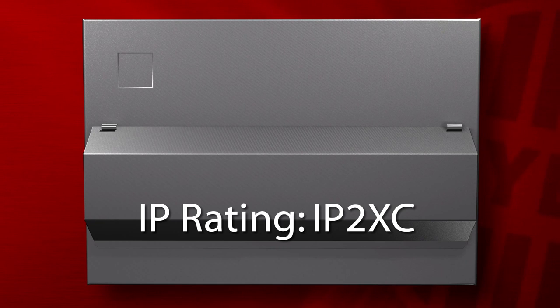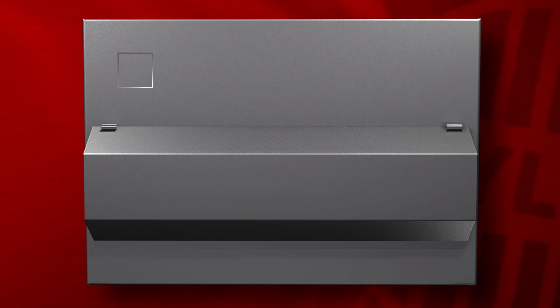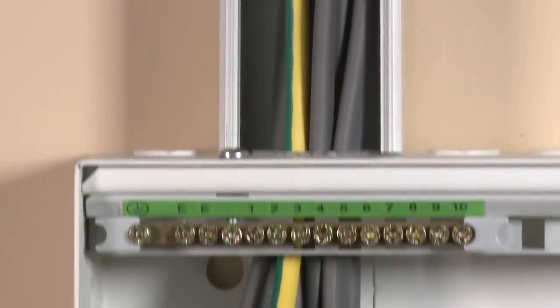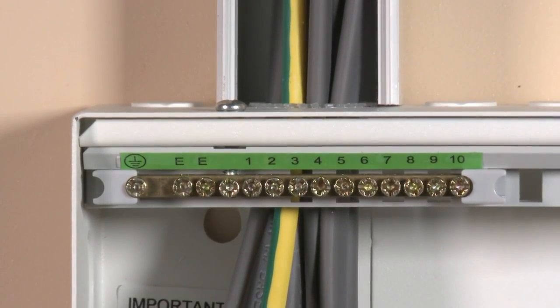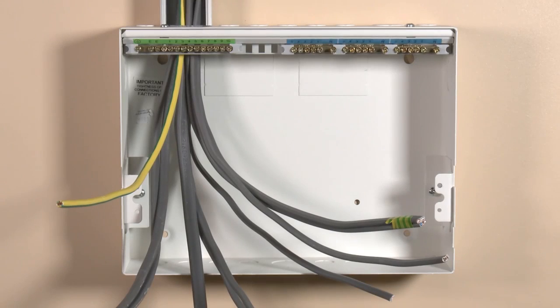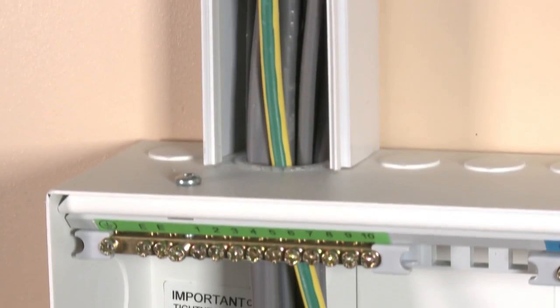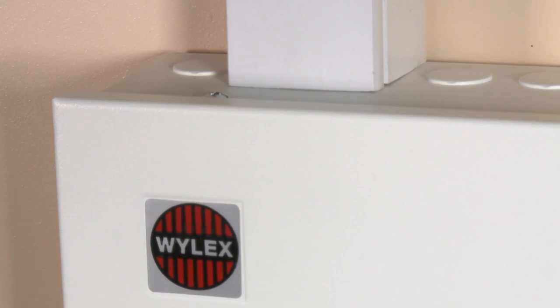This can be achieved in many ways. The following are examples of methods that may be used, including the use of a mains tails gland. In our first example, all cables enter the enclosure via a single entry point with the trunking system installed, so as to provide a barrier to assist achieving the necessary IP rating where the outgoing cables and consumer unit meet.